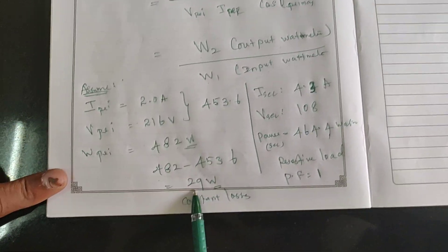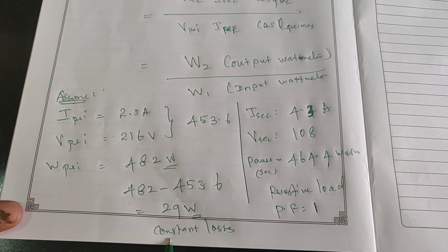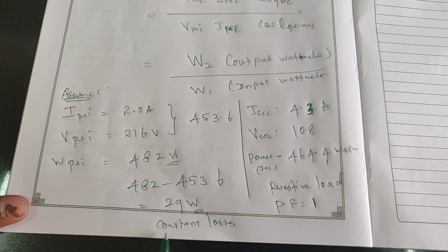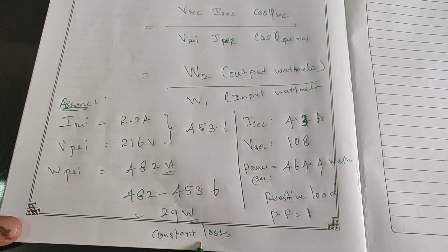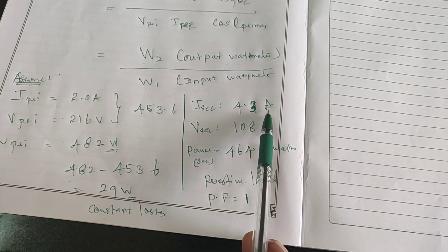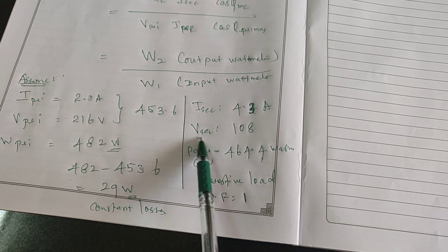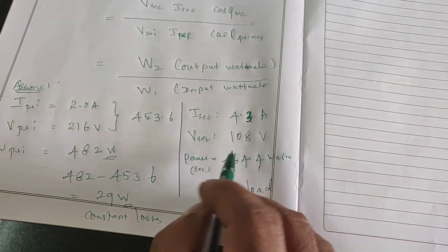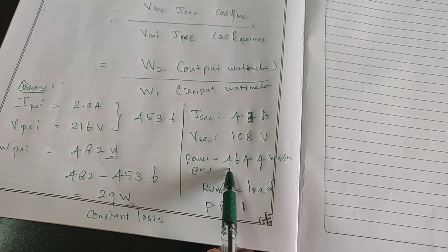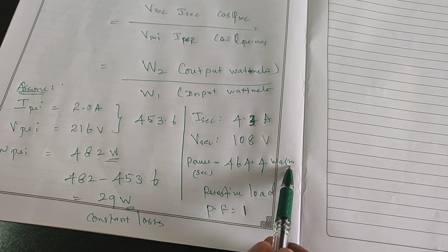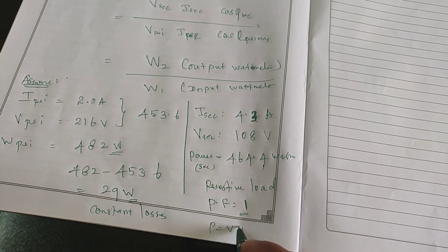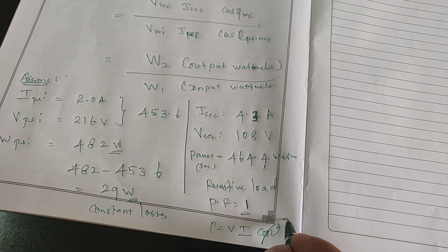The change of 29 watts indicates losses. On the input side, this amount of power is consumed for constant losses — I can say these are the iron losses. Similarly, on the secondary side, 4.3 amperes of current is consumed at the load and voltage is equal to 108 volts. Therefore, the power calculated is 108 × 4.3 = 464.4 watts. Since it is a resistive load, the power factor is unity, so power = V × I only, because cos θ = 1.